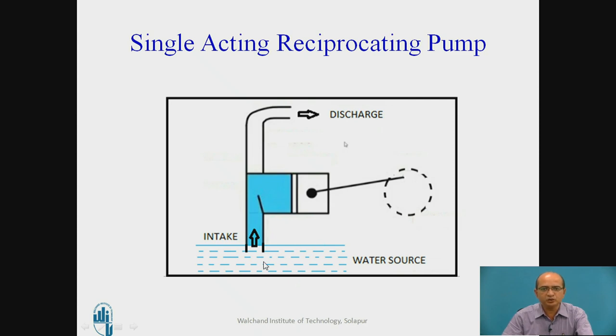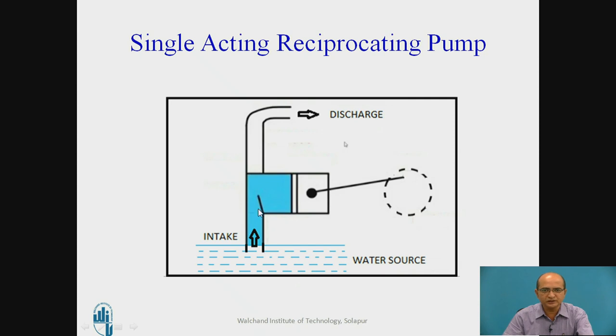In this pump, a foot valve is not required, unlike the centrifugal pump. During suction, water automatically rushes in and is then discharged through the delivery pipe. In the centrifugal pump, if the foot valve is not provided, water returns to the well through the pipeline instead of being retained in the casing. But in the reciprocating pump, when there is no piston movement, the suction valve is closed and water inside remains as it is during the idle condition.